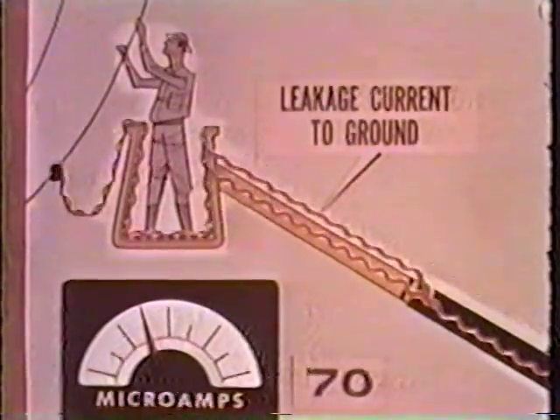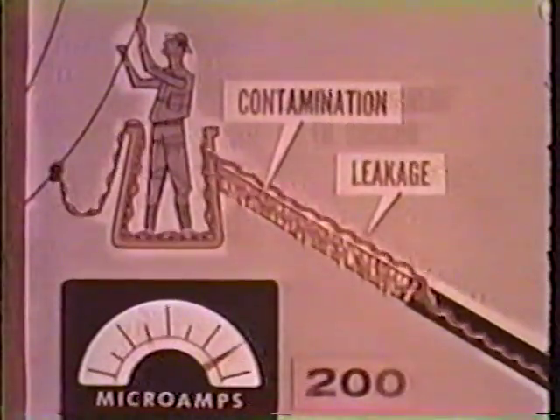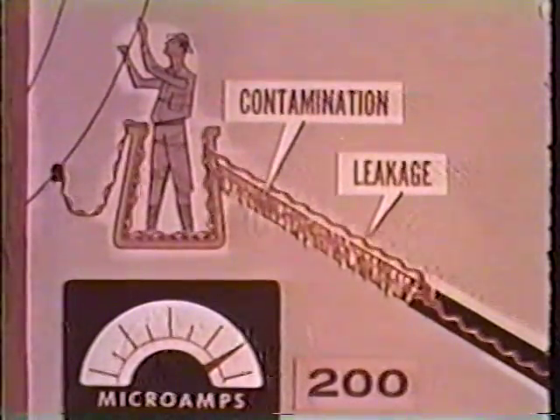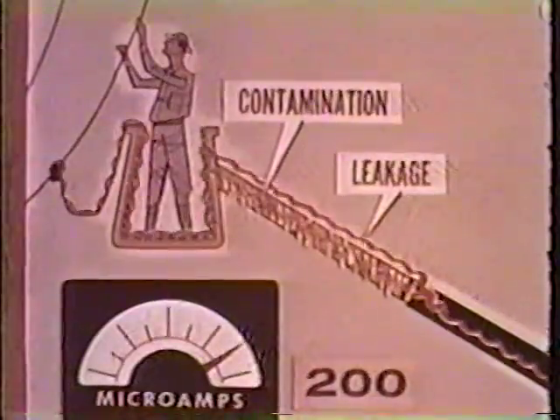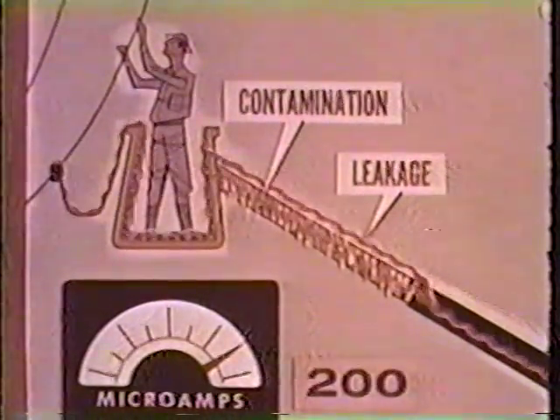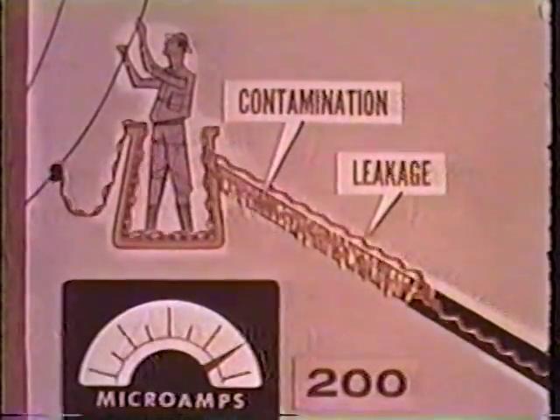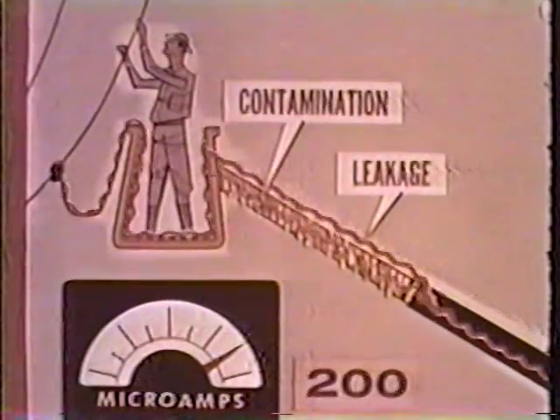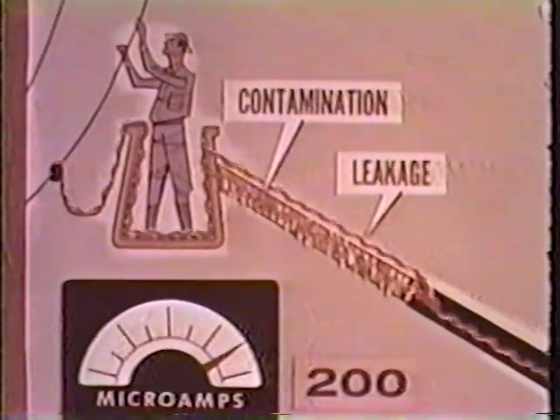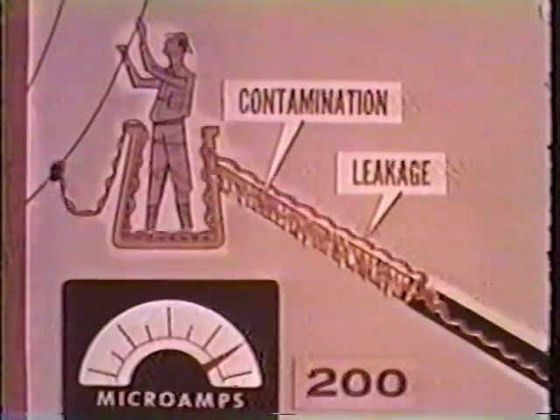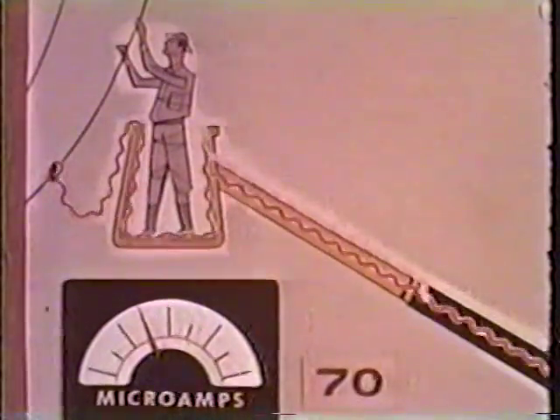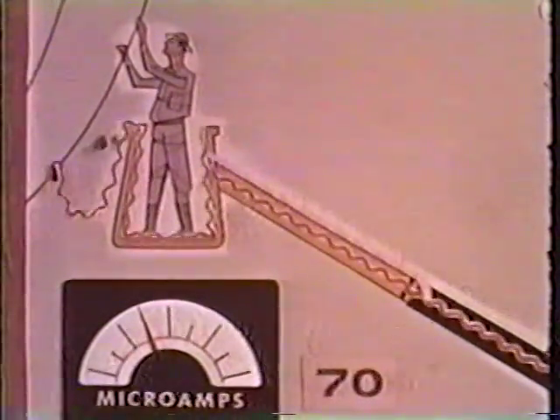Under severe conditions, this can produce an arm current reading of 200 microamperes or more. At the 200 microampere level, the arm is still safe, but should be cleaned. At readings above this level, the unit should be checked and serviced to restore the arm current to its original low level.